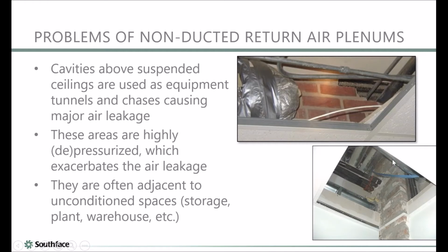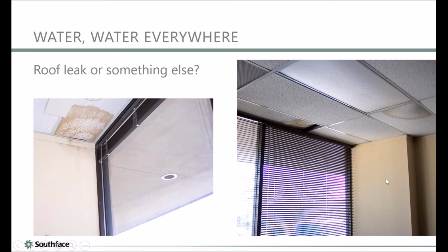I did want to show a picture of it having been done right. This is a case where fire code actually kicked in and they did seal the penetrations. But that's kind of uncommon. Right. The other thing is that I think almost any person on the planet has been in a commercial building and seen water stains on the drop ceiling. Yep. I don't think anybody's never seen that. So that's a fairly common occurrence. And 99 out of 100 times, that is not a roof leak or a plumbing leak. And Laura, what is that? What's the source of that?